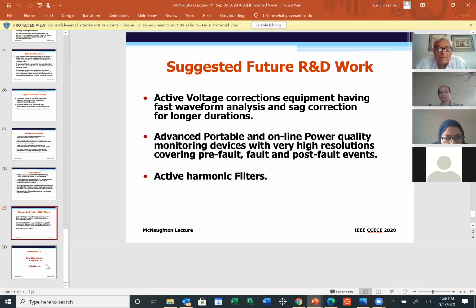The other one: it will help if you have advanced portable or online power monitoring devices with higher resolution that can basically capture pre-fault, fault, and post-fault. And of course, the last one, which already exists in the industry, is what we call the active harmonic filter, rather than using a passive harmonic filter. The reason I felt this could be suitable for graduate students is that this area combines power, electronics, control, and communication. So it's not just power, and this is where the interest is.